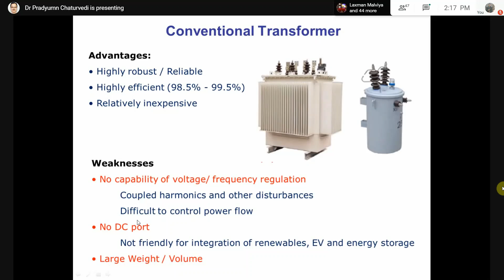Now what it will do and what duties it will perform. In this traditional MVAC bus, the communication is based on IEC standards and some other standards for smart communication. On the other side, this SST will give you the flexibility of implementing a low voltage DC bus separately and a low voltage AC bus separately. That means you have a multi-port, multi-voltage system at the DC side and AC side, so you can connect DC sources and loads at one side and AC load and AC source at the other.